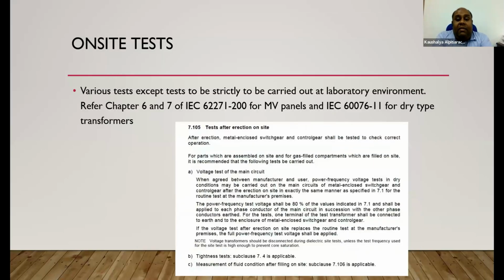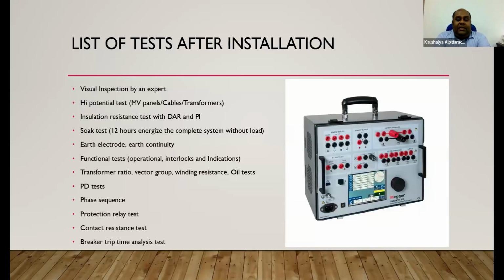And test after installation. Voltage test for main circuits. This is again called the high voltage test or high pot test, and it is said to be tested at 80% of the power frequency test voltage, and so on. You can refer to chapter 7 of 62271-200, and a list of other standards, other tests.